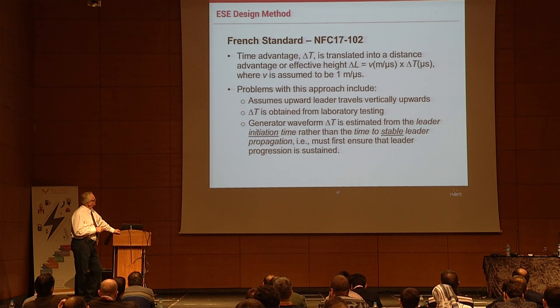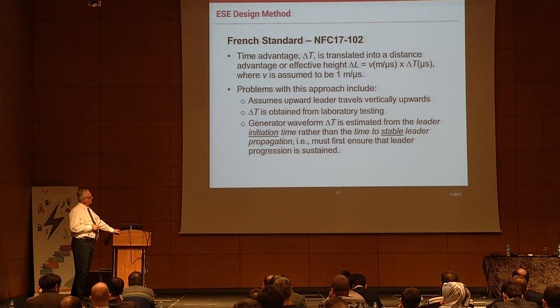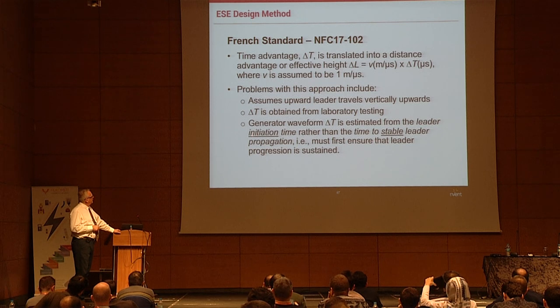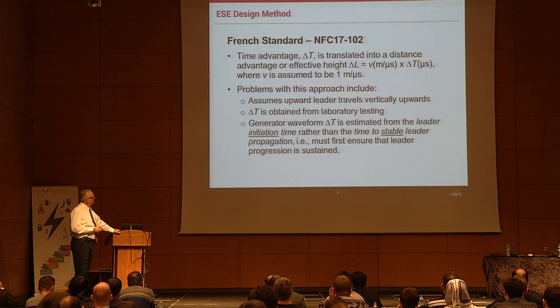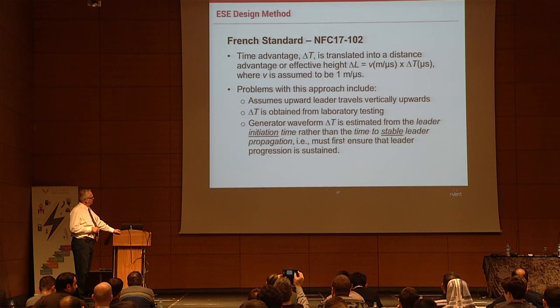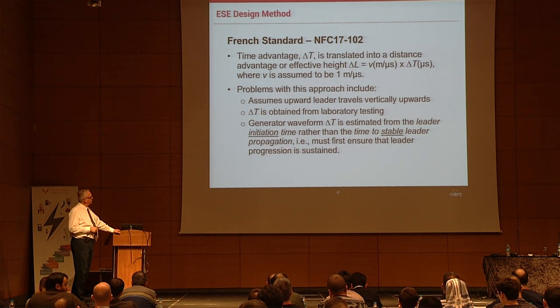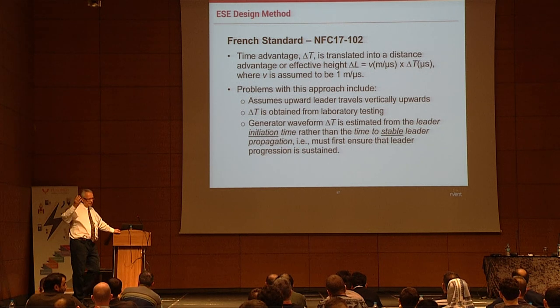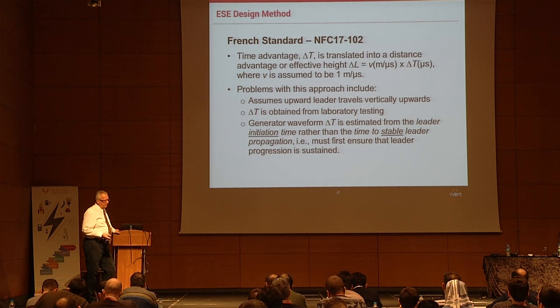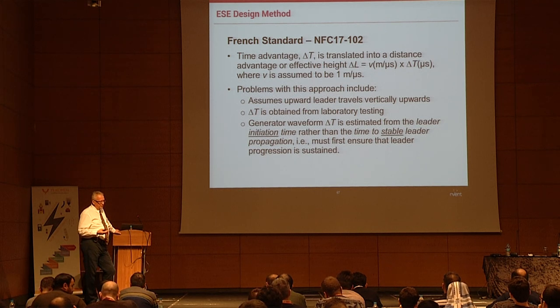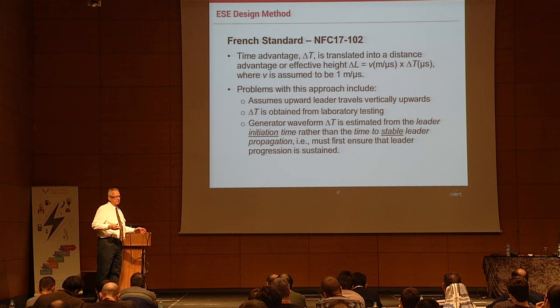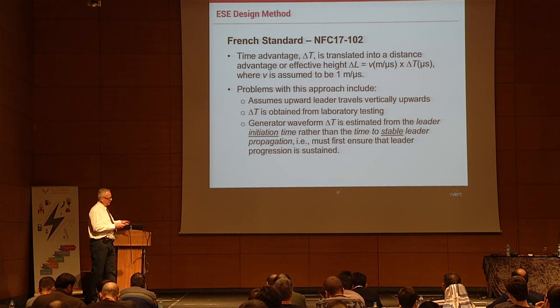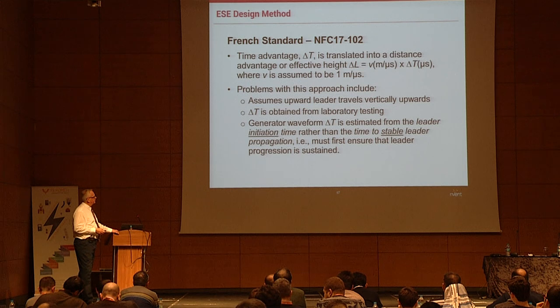One of the bigger assumptions in the NFC standard is that the generator waveform delta T is estimated from the leader initiation time rather than from the time to stabilize the leader propagation — meaning it doesn't properly account for how the leader propagates through the atmosphere.